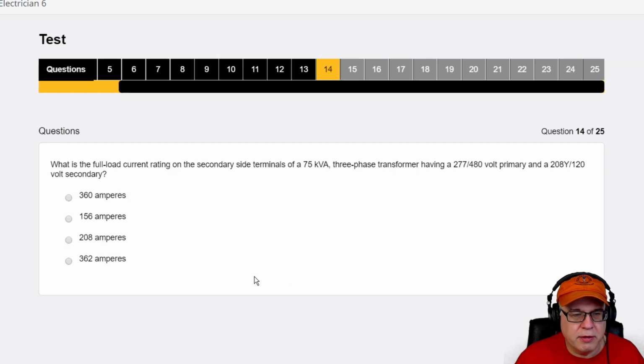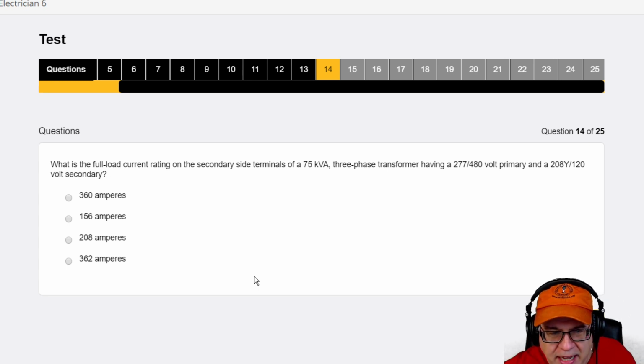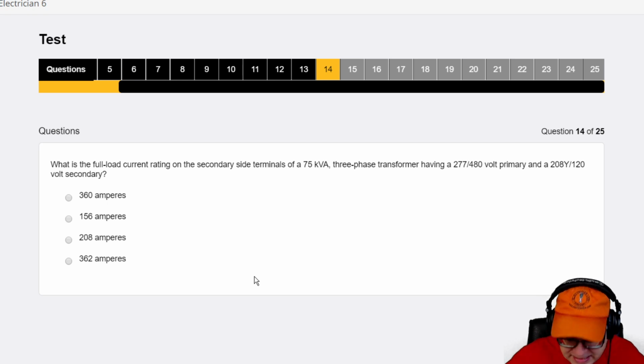What is the full load current, FLC, rating on the secondary side terminal of a 75 kVA 3-phase transformer having a 277/480 volt primary and a 208Y/120 volt secondary? Great question, probably the kind you'll see on an exam.